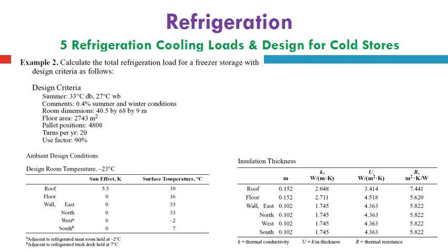This slide presents example number 2, which is dedicated to calculating the total heat load after we have finished all the expected load components: the transmission load, the internal loads due to people, lighting, motors, or any equipment, the infiltration load, and the product load. So for this freezing storage, the design criteria are listed here. The summer design is 33 degrees Celsius dry bulb and 27 degrees Celsius wet bulb.